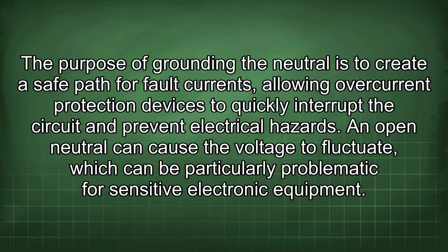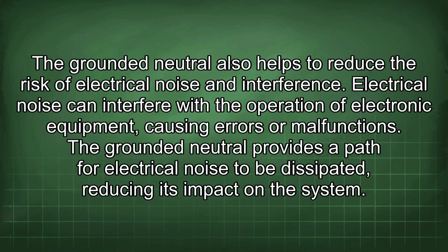An open neutral can cause the voltage to fluctuate, which can be particularly problematic for sensitive electronic equipment. The grounded neutral also helps to reduce the risk of electrical noise and interference. Electrical noise can interfere with the operation of electronic equipment, causing errors or malfunctions. The grounded neutral provides a path for electrical noise to be dissipated, reducing its impact on the system.